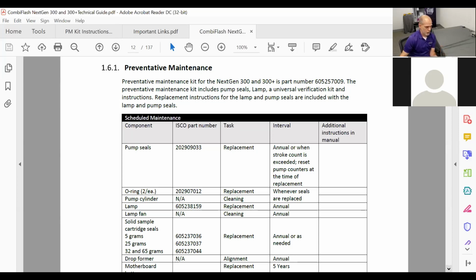All right. Now, some of the things that you're going to find here, again, pump seals. We do recommend that you do that annually or whenever your unit is telling you that the pump strokes are exceeded. That is resettable in the service menu. I'll show you that later. But there's a counter inside there that's counting. Some units it's 100,000, some units it's 200,000 strokes. But as you approach that number, the unit's going to start to give you warnings that you're getting close to the lifespan of your seals. If you go over that count, it's going to tell you to contact someone to replace those seals.